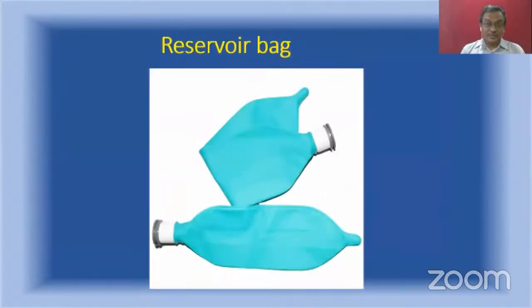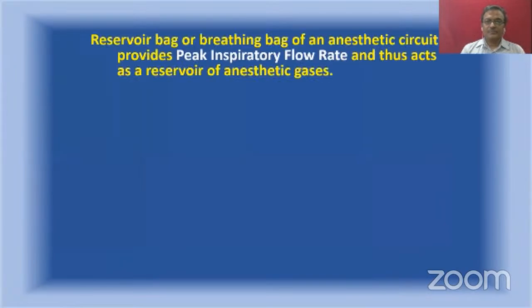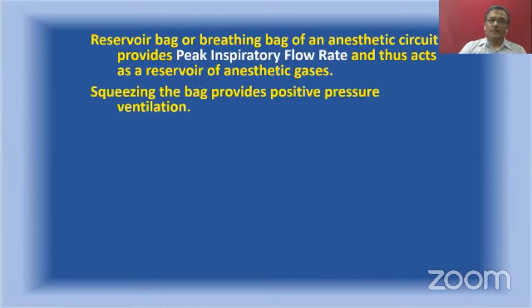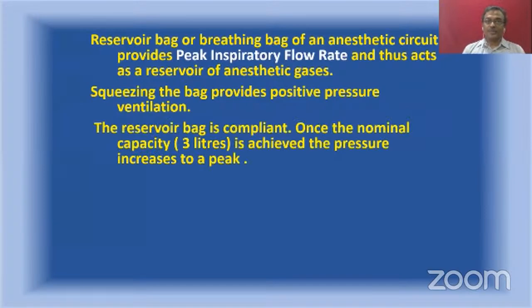Now, something about reservoir bag, because it's a very important component of the anesthesia circuit. You know the function of reservoir bag. It is known as breathing bag also because it provides the peak inspiratory flow rate, PIFR, and thus acts as a reservoir of anesthetic gases. That's the first function. Second, you can have visual and tactile perception of the respiratory movement. And you can squeeze the bag and provide positive pressure ventilation. And there is one more important function for the reservoir bag, that is, it is a compliant bag.